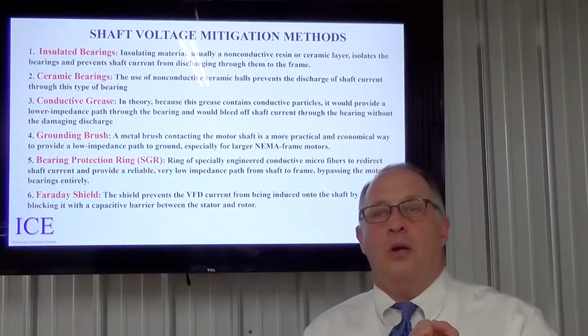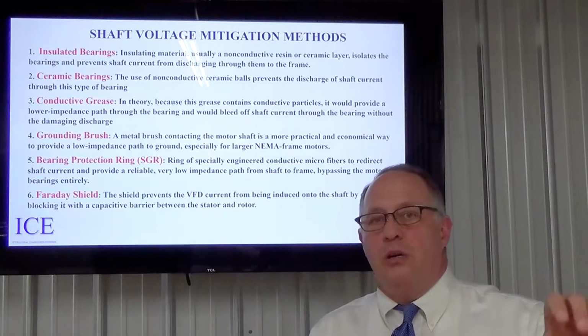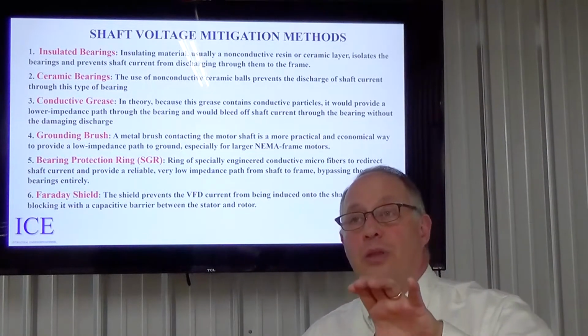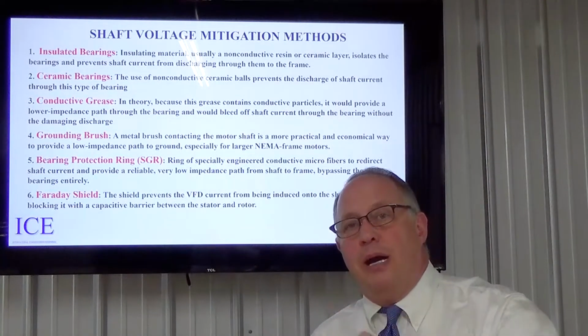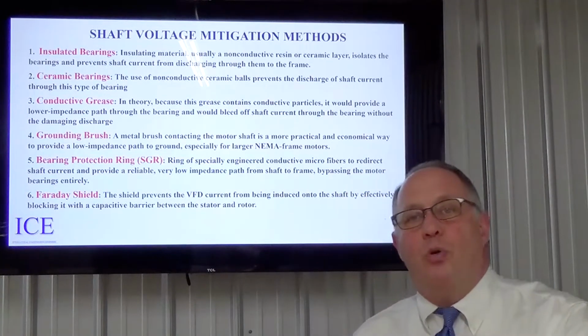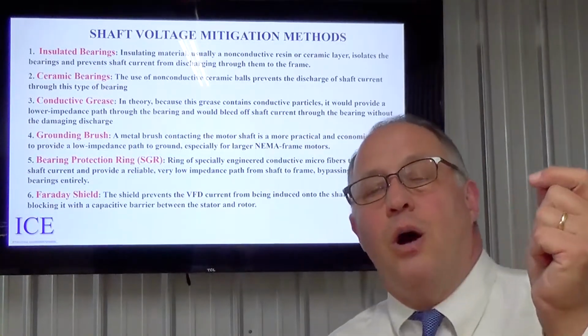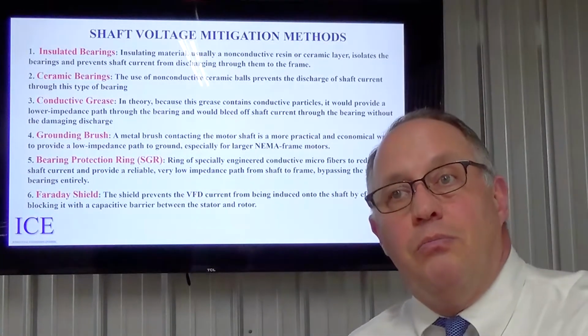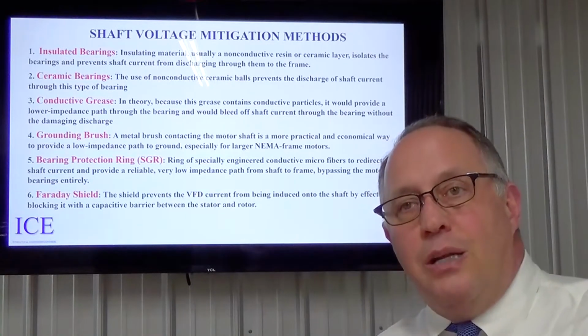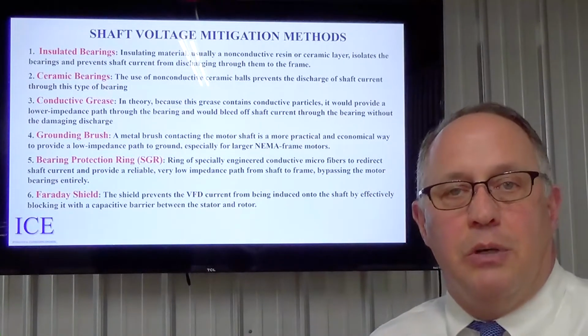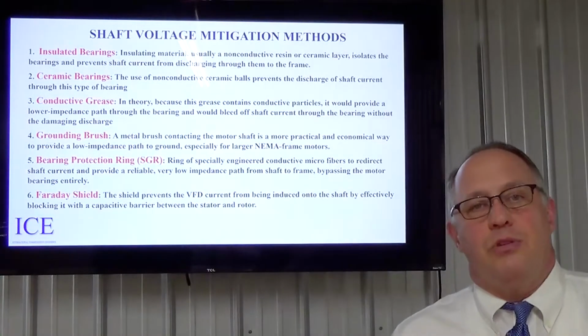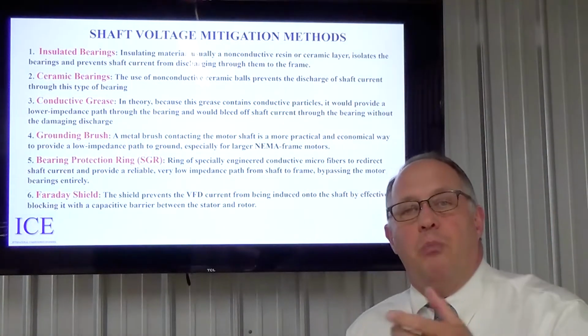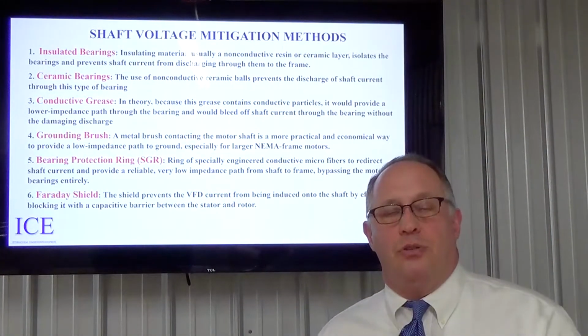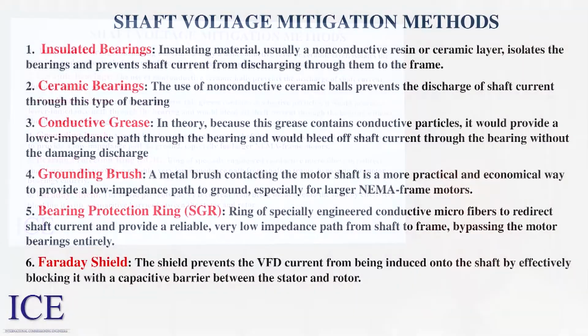Once again, we have shaft voltage produced on the outer race bearing, but it doesn't have a way to arc over because the ball itself is made out of a non-conductive material. Once again, it still leaves a shaft voltage there, but it doesn't have a path to ground through a damaging arc current. Number 3, conductive grease.